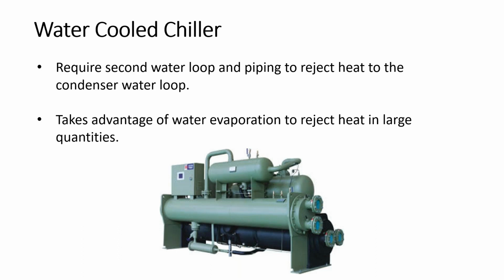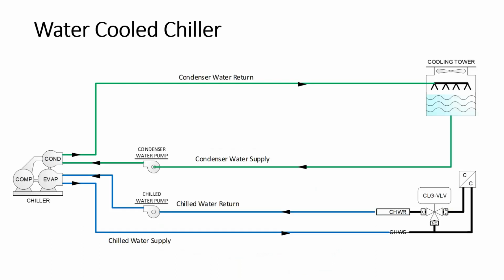Using large amounts of refrigeration, we've got to reject the heat in large quantities. So we need water cooled to do that, and we use the evaporating effect of water. So here's a typical system. Again, we're constant volume on both sides. So we pump the water through the chilled water loop into the evaporator. It picks up the heat out of the water, transfers it to the condenser where we reject it to the cooling tower on the outside.